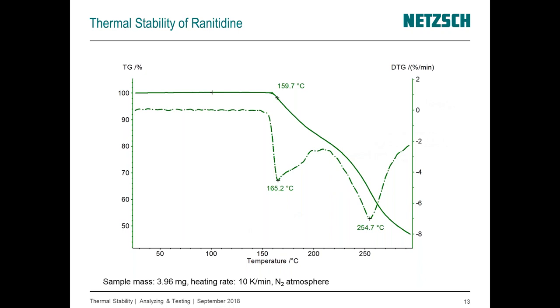As another example, ranitidine is a pharmaceutical ingredient for the control of gastric acid production, heartburn, or treatment of reflux diseases. You can see the measurement parameters given below. The result shows the TG result over temperature, and the dashed line refers to the rate of mass change. Since we are especially interested in thermal stability, the material is not changing its mass up to about 160°C, and then we have a two-step decomposition mechanism.